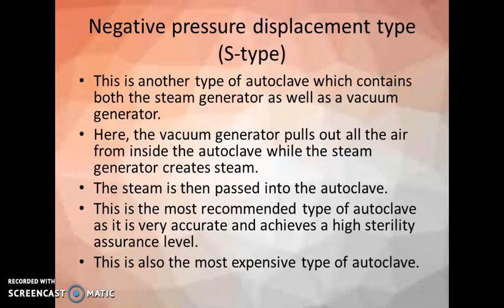The next type is the S-type or negative pressure displacement type. This is also another type of autoclave which contains both a steam generator as well as a vacuum generator. Here, the vacuum generator pulls out all the air from inside the autoclave, so all the air is removed through the vacuum generator while the steam generator creates the steam. Then the steam is passed into the autoclave. This is the most recommended type of autoclave, and it is very accurate and achieves a high sterility assurance level. This is also the most expensive type of autoclave.